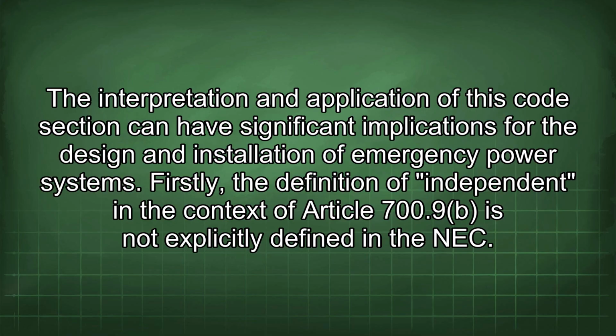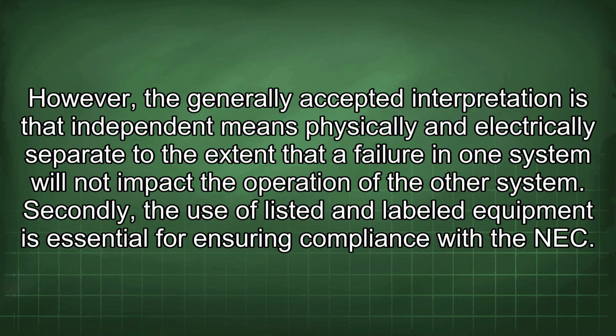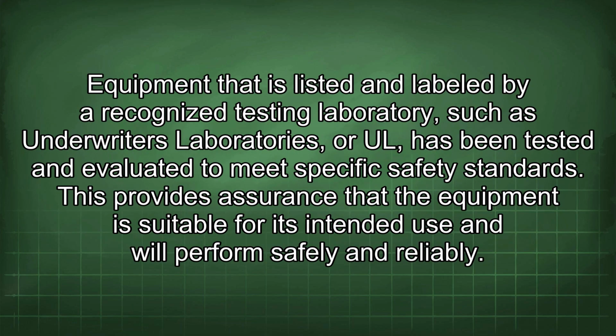Firstly, the definition of independent in the context of Article 700.9 is not explicitly defined in the NEC. However, the generally accepted interpretation is that independent means physically and electrically separate to the extent that a failure in one system will not impact the operation of the other system. Secondly, the use of listed and labeled equipment is essential for ensuring compliance with the NEC. Equipment that is listed and labeled by a recognized testing laboratory, such as Underwriters Laboratories, or UL, has been tested and evaluated to meet specific safety standards. This provides assurance that the equipment is suitable for its intended use and will perform safely and reliably.